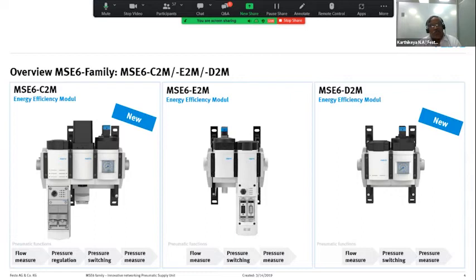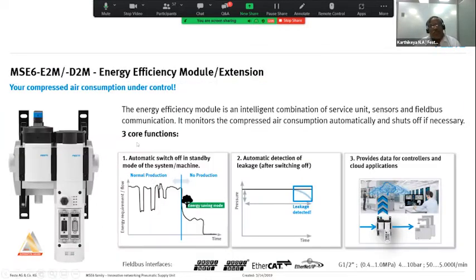The module units help us to have different functionalities, like MSE6-C2M, E2M and D2M. Here you have pressure, flow and pressure regulation, whereas in the other two you have only pressure measuring, flow measuring and pressure switching functionalities. As you have seen in the previous video, we have three core functionalities. One is auto shut-off functionality, another is automatic leak detection, and also taking the data to the cloud. And here we have different interfaces depending upon the PLC. Therefore, it can be used as a slave module to the master PLC.